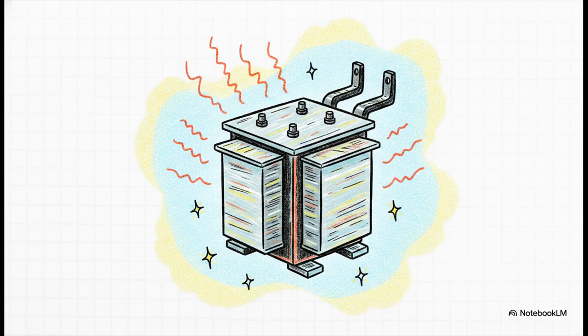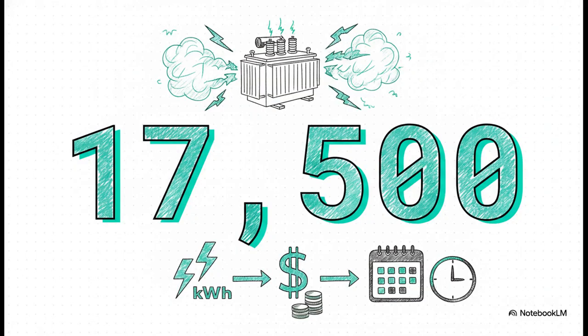And this brings us to a really crucial, often totally overlooked paradox in power engineering. An idle transformer burns power just by magnetizing its own core. Literally, the exact second you close the breaker and energize it, you start paying for core losses. So zero load connected to the building absolutely does not equal zero loss at the transformer. Let's put a real number on that so you can see what I mean. A standard 1,000 kVA transformer with just 2,000 watts of no-load core loss will waste roughly 17,500 kilowatt-hours a year, doing absolutely nothing but sitting there energized.